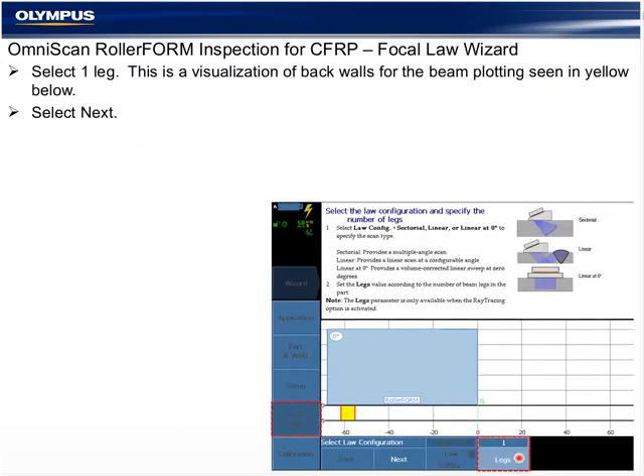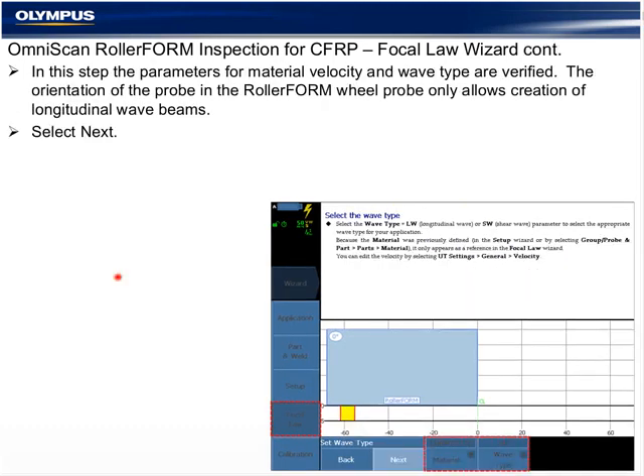Select leg 1, which represents the beam plotting for the inspection. These inspections are going to be a single leg inspection between the probe or the water to tire material interface on the component to the back wall. The material was selected during the setup, and the wave type is not selectable here because this type of probe and wedge or water only generates a longitudinal wave type. So skip through this and select next.